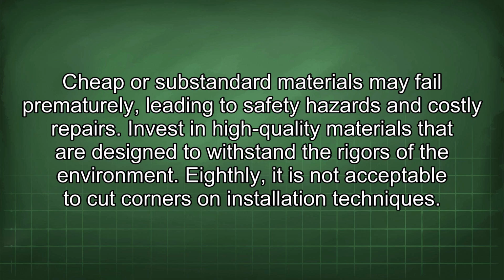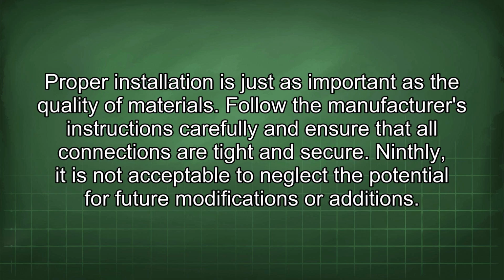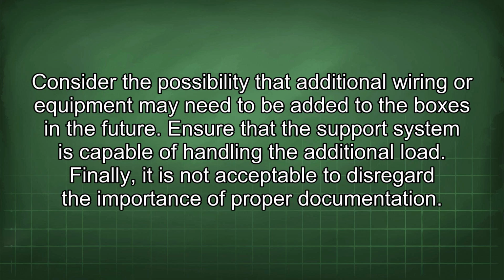Eighthly, it is not acceptable to cut corners on installation techniques. Proper installation is just as important as the quality of materials. Follow the manufacturer's instructions carefully and ensure that all connections are tight and secure. Ninthly, it is not acceptable to neglect the potential for future modifications or additions. Consider the possibility that additional wiring or equipment may need to be added to the boxes in the future. Ensure that the support system is capable of handling the additional load.